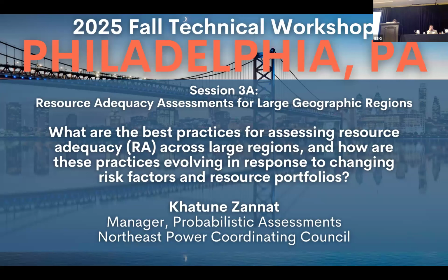NPCC's resource adequacy reports highlight both independent efforts and collaboration with NERC and the broader ERO Enterprise, and align with the evolving vision for wide area energy reliability assessments. At NPCC, we use probabilistic modeling to simulate thousands of scenarios of extreme weather, fuel disruption, and demand spikes to quantify reliability risks, estimating when and how operating procedures will be needed to avoid any shortages.